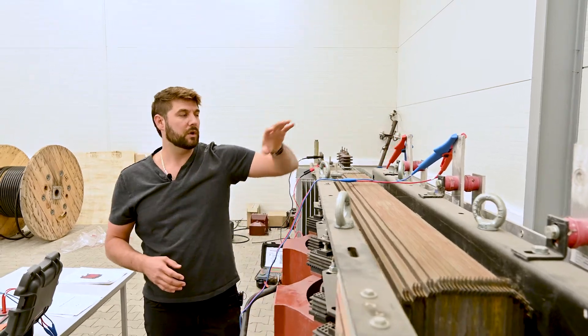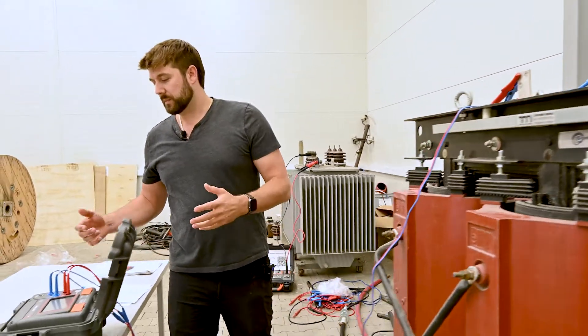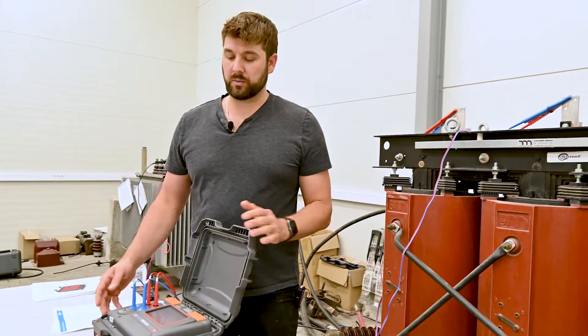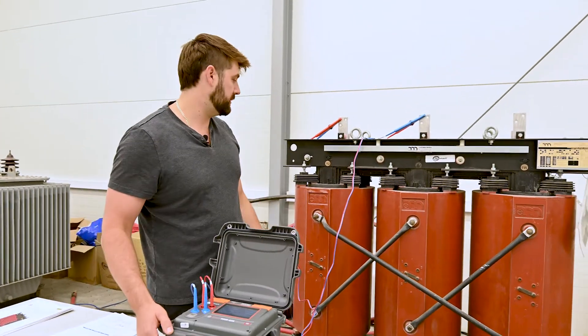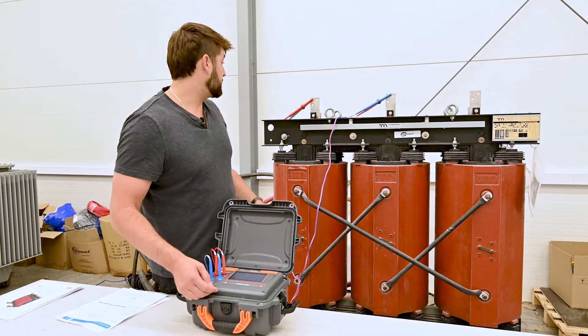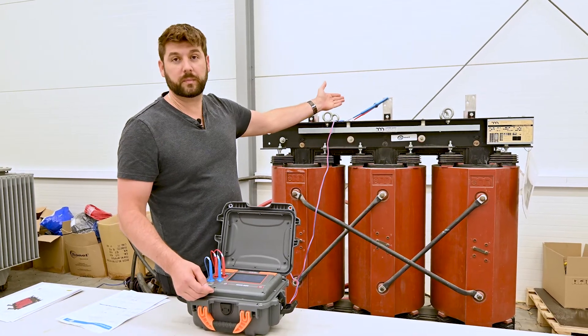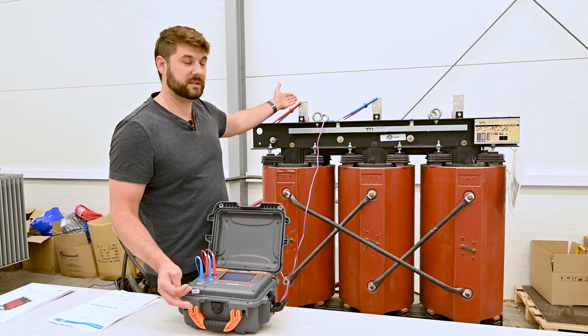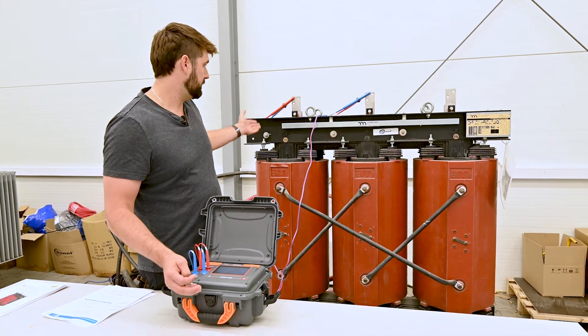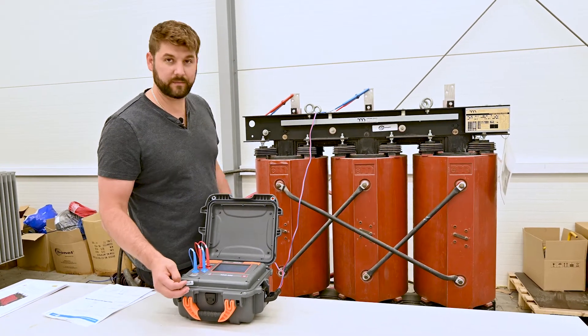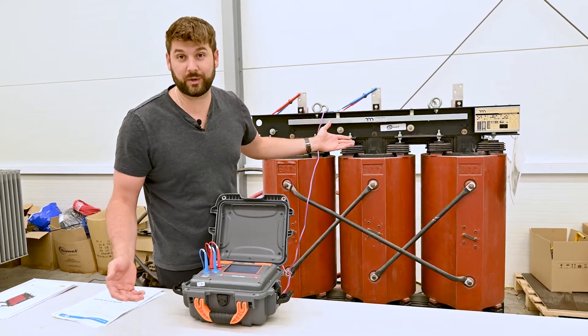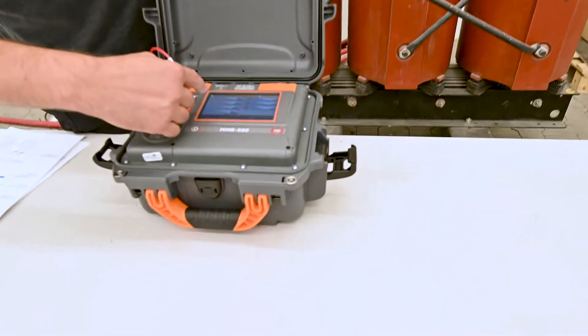We're looking for a resistance value somewhere in milliohms, making sure that we have a good winding. Basically, you're just hooking up between the phases. Of course, the way they're connected, this is the only way you can hook up to a transformer.